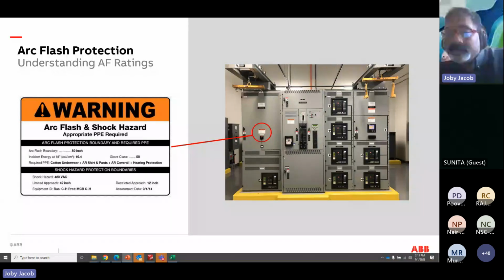And normally we try to paste it on every feeder panel, whether it is low voltage or medium voltage. The required arc flash study is calculated and the arc flash label is pasted, and it will give you the incident energy in a condition where the panel doors are open. So normally, as per the IEC requirement, if all your panel doors are closed, the arc flash should be contained inside. But in reality, it doesn't happen because of poor maintenance, or if the criteria they are telling is not met, then it will propagate out. Then it will recommend the required PPE, and the limited approach boundary, the restricted approach boundary, and all those things will be mentioned in the arc flash label.